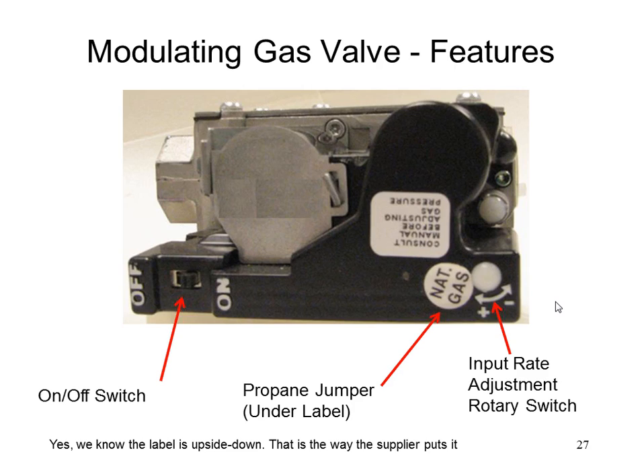However, with this modulating gas valve, it's a little bit different. You actually set the low end, and then you stop, and then you redo it again and set the high end, and then it has those two pieces from the lowest fire to the highest fire, and it knows how to operate in between there. So you really only have to calibrate that thing as a one-time process. You don't have to keep going back and tweaking it to make sure you got it right. You calibrate the low and the high, and everything in between is fine.